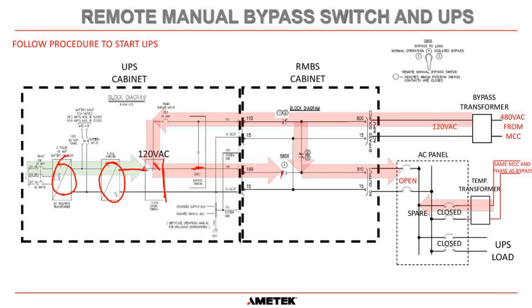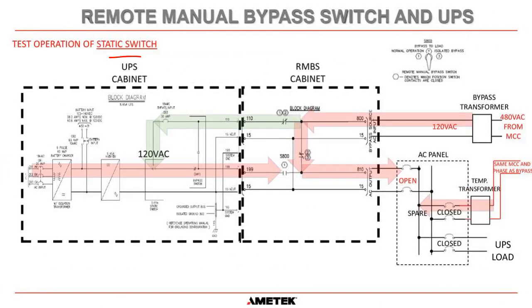We have voltage going to that contact there in the RMBS cabinet, but it is still in the open position. What that allows us to do is test the operation of the static switch inside the UPS. So we can actually turn this static switch on and supply power to there, and we can transfer it from inverter to load, bypass to load, and make sure the transfers are okay before we say, okay, everything looks good. Our UPS is now back in full operation.